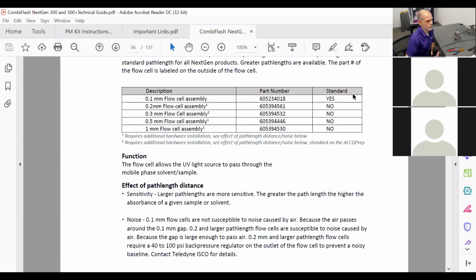Something you need to be aware of, though, and that's something called noise. So on your chromatography, you might notice it looks like a lie detector test, like grass. It's just spiky. That's noise, and that can be caused by air bubbles. It can be caused by pressure dips. It can be caused by a few different things. But if you've got air bubbles trapped in your flow cell, it can get caught in the gap, and you may have no detection, but good light.